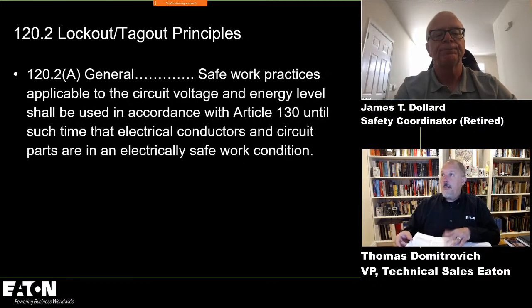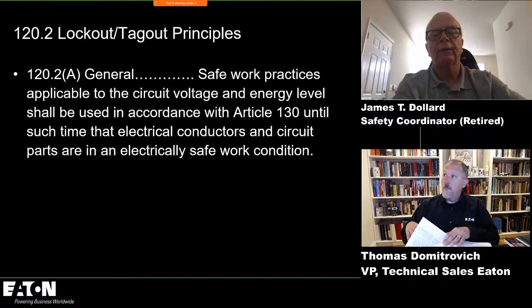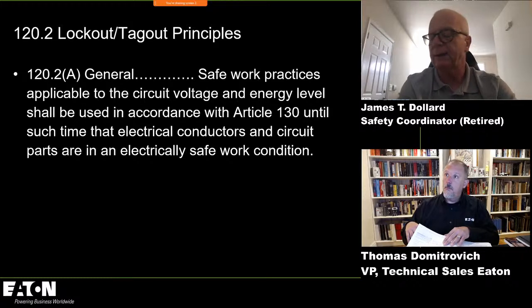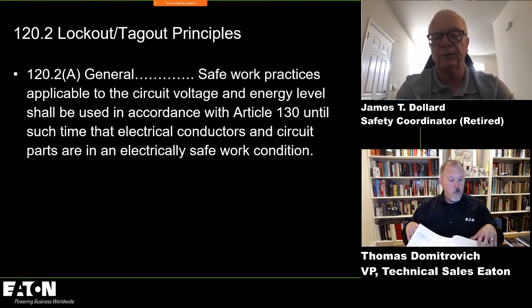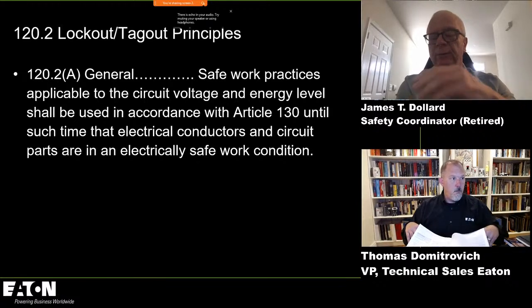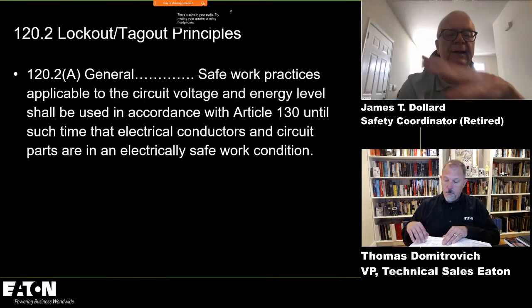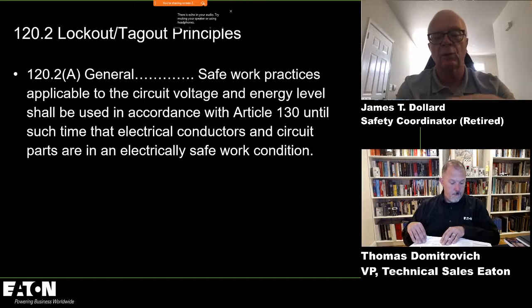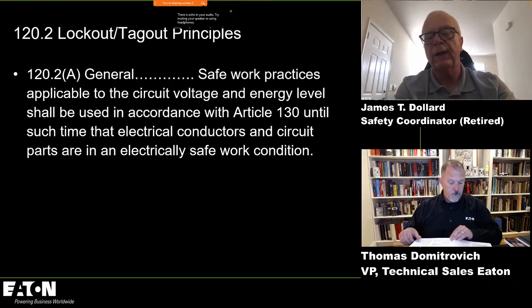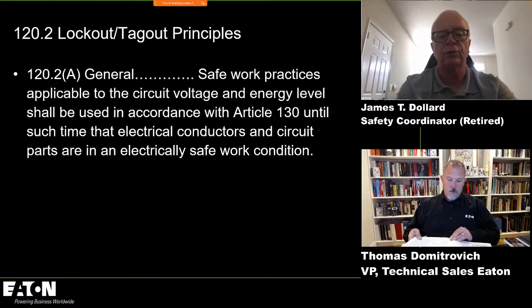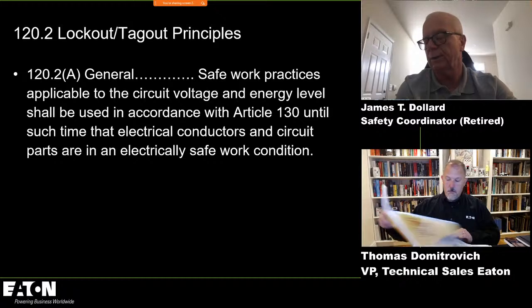120.2 gets into your lockout and tagout. You have complex and simple, right? Yeah, the only thing, I didn't think we'd have time to get into those, but this is included here because in 120.2(A) general, this is where we tell you that safe work practices, which means shock risk assessment, arc flash risk assessment, identify the PPE, okay? So all of that, we have to do in accordance with Article 130 until such time that electrical conductors and circuit parts are in an electrically safe work condition.